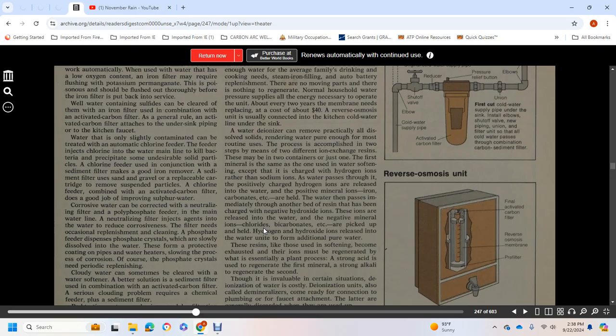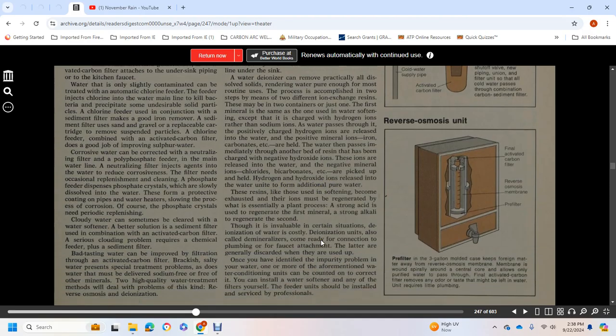As water passes through, positively charged hydrogen ions are released into the water. Positive mineral ions, iron, carbonates, and so on are held. The water then passes through another bed of resin that has been charged with negative hydroxide ions. These ions are released into the water. Negative mineral ions such as chlorides, bicarbonates, etc. are picked up and held. The hydrogen and hydroxide ions released into the water unite and form additional pure water.